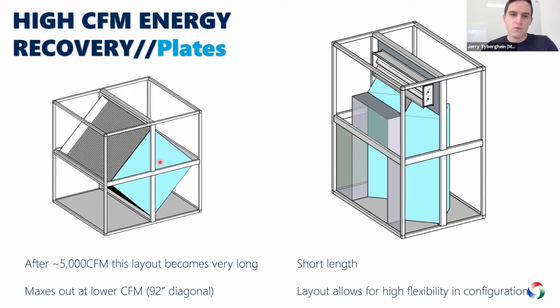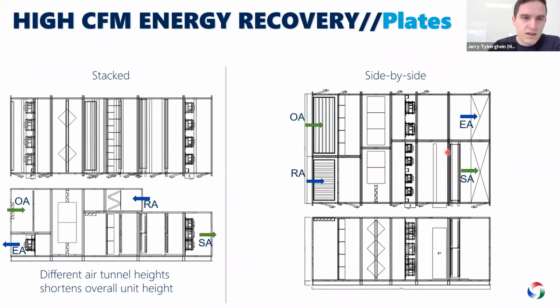On the right, what we do is take smaller heat exchanger modules and stack them in rows. You can see these sheet metal blank-offs right here. They allow you to route the air properly so that the air goes through the heat exchanger. So if you can understand this concept, I'll show you some CAD drawings now. On the left is a stacked unit, on the right is a side-by-side unit. Let's focus on the left one first.